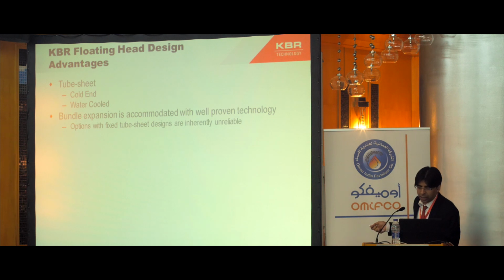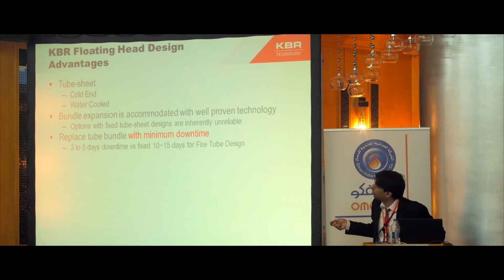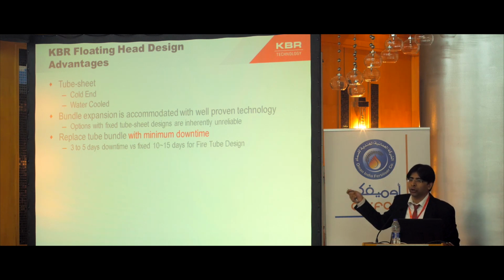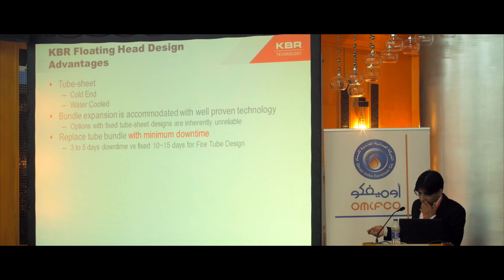Coming to the advantages of this floating head design, the tube sheet is cold end and water cooled, which is at the top. The tube to tube sheet joints result in a cool joint operating at the boiler feed water temperature, resulting in a reliable design with proven fabrication techniques. Bundle expansion is accommodated with well-proven technology. At the bottom an expansion joint is there, which results in zero stresses. This removable bundle design allows the operator to replace the complete bundle with a spare if needed. Typical downtime is around 3 to 5 days.